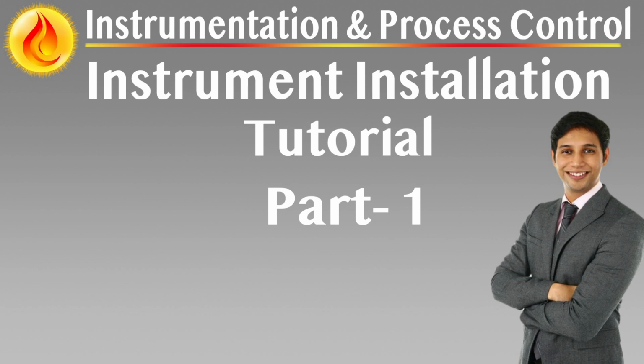Direct mounting, compact design with integrated functionality. In direct mounting applications, the instrument is affixed directly to the process connection, often using a flanged gauge block or integrated manifold block. For pressure gauges, flanged gauge blocks offer structural support and standardized alignment while preserving measurement fidelity. More advanced configurations consolidate the primary isolation valve and instrument manifold into a single compact housing, commonly referred to as a monoflange. These integrated components reduce leak paths, minimize installation time, and simplify overall footprint.